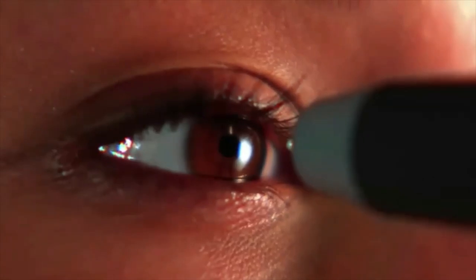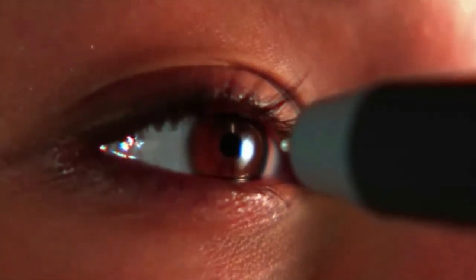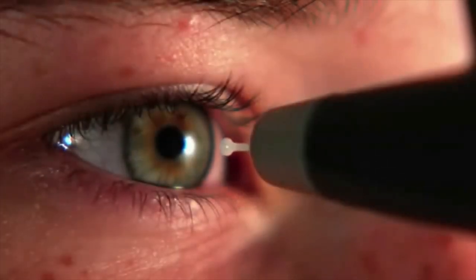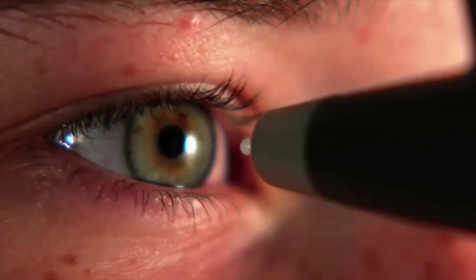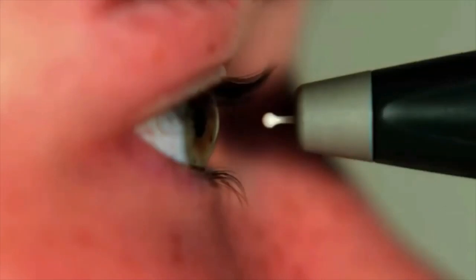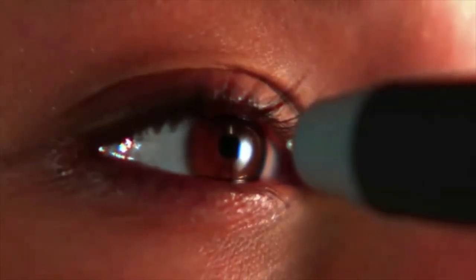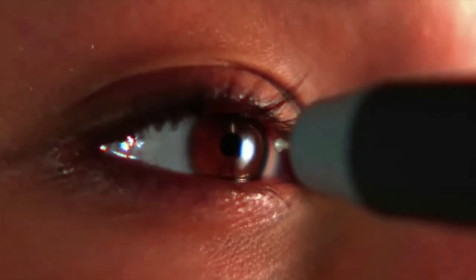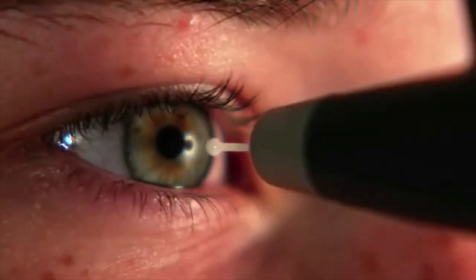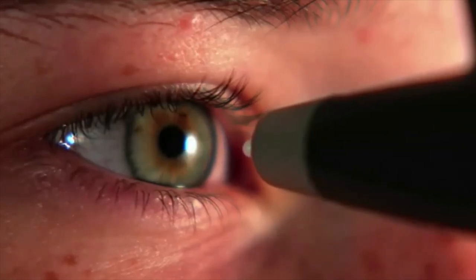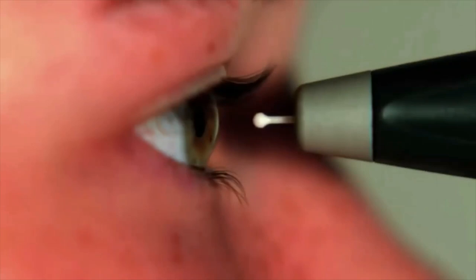So what I'm going to show here is a sample of technical replicates generated by one of the eye care tonometers, which are portable handheld devices used to measure intraocular pressure. Compared to the old Goldmann tonometry, measuring intraocular pressure gets much easier than ever with this type of device. So in this high-resolution slow-mo video, the device measures intraocular pressure with a tiny probe by gently drumming down on the cornea 6 times in a split second, and it'll provide the accuracy and precision of the given measurement.